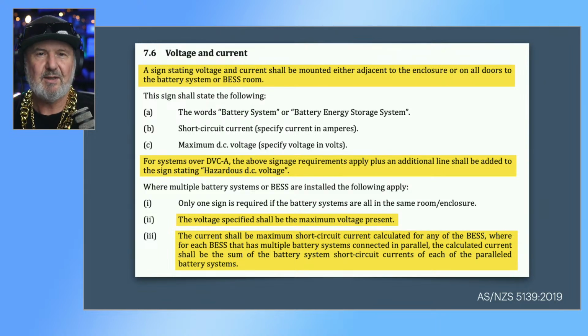Martin says, are systems installed prior to 5139 required to add this labelling? We've never been retrospective with any of our Australian New Zealand standards. The only time something kind of retrospective applies is if you modify the power, voltage or current of a system, you need to bring it up to current standards. So no, Martin, you don't have to go back and relabel all those old systems. Just beware, if you do change anything, unless it's a like-for-like swap, it may be a requirement to meet the new standards.